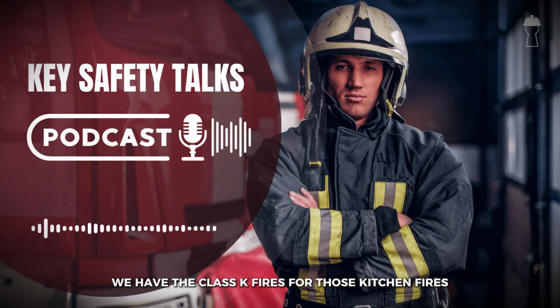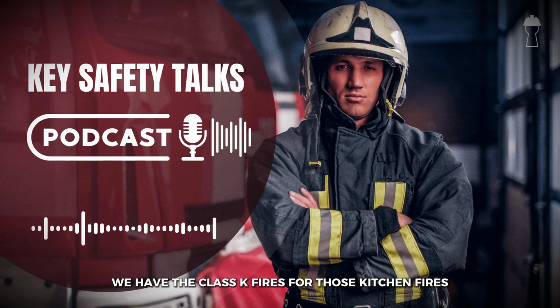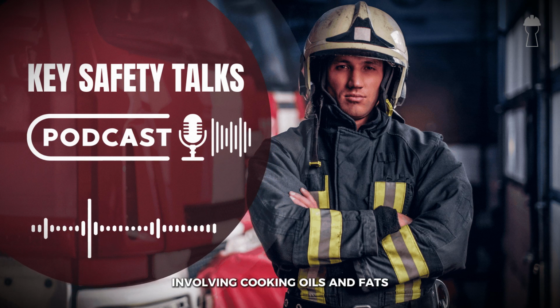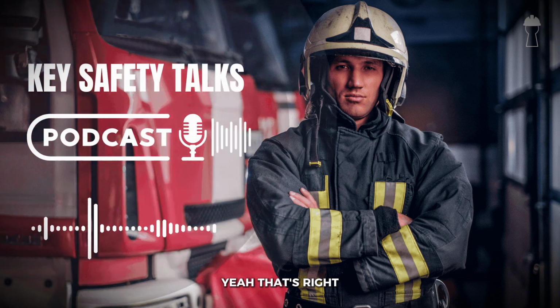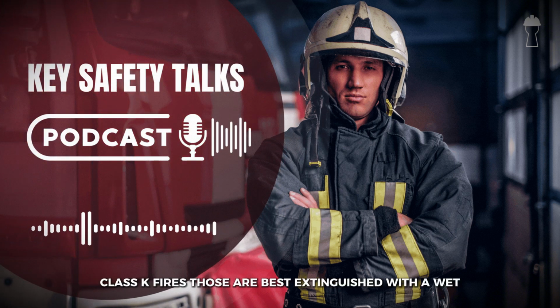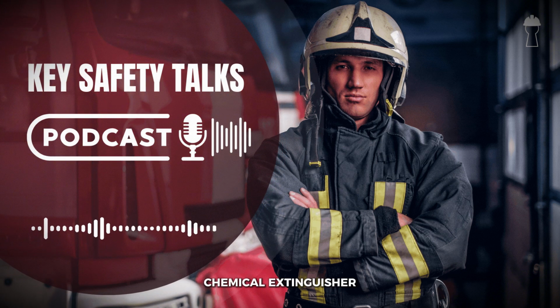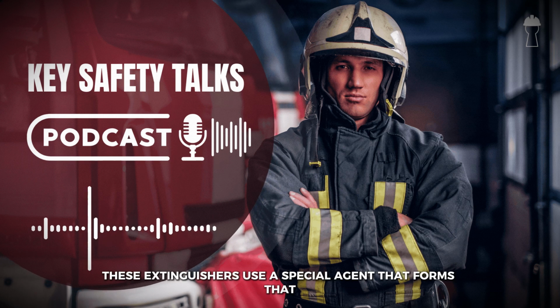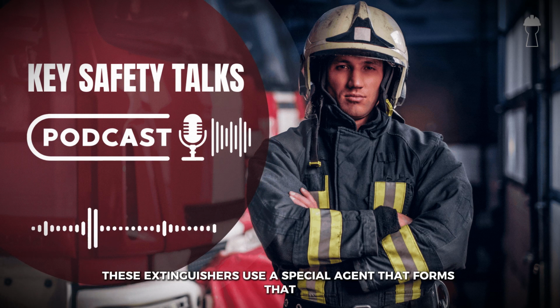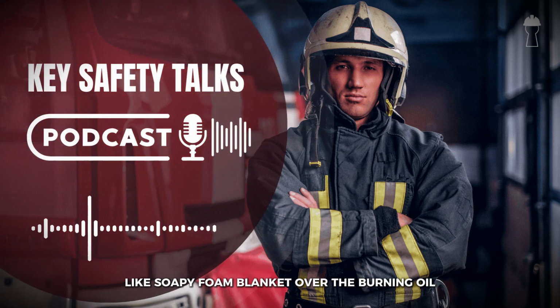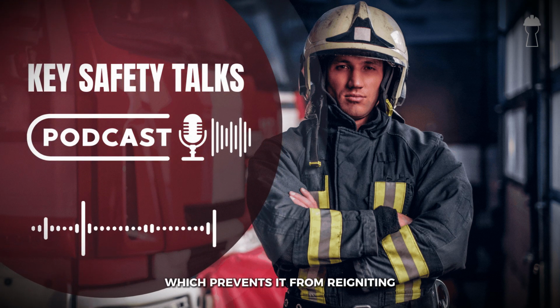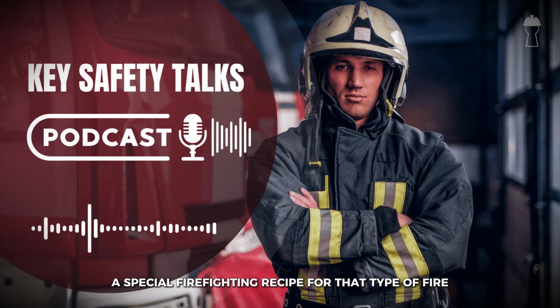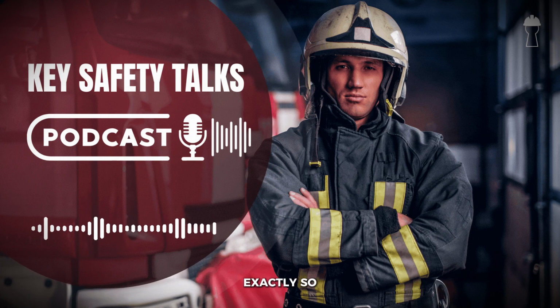And then, of course, we have the Class K fires for those kitchen fires, involving cooking oils and fats. Yeah, that's right. Class K fires are best extinguished with a wet chemical extinguisher. These extinguishers use a special agent that forms a soapy foam blanket over the burning oil, which prevents it from reigniting. So it's like a special firefighting recipe for that type of fire.